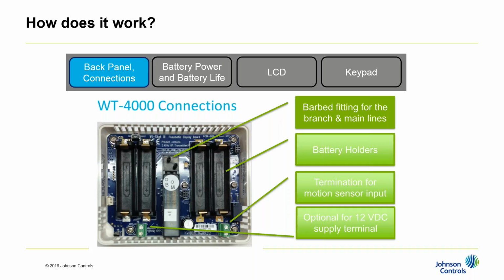A little more on how this works. In the past, we had a bimetallic strip that would change physical shape to release or allow more air to the pneumatic load. Now we've taken a more digital approach. That valve in the middle of your screen is a piezo valve, a medical grade valve. We take the mainline pressure and feed it to the branch line, and we can either increase pressure by bringing in more mainline pressure or bleed off pressure on the branch line. It's very precise control - we have a PID loop that controls all of it, and it requires no calibration because it's completely digital.